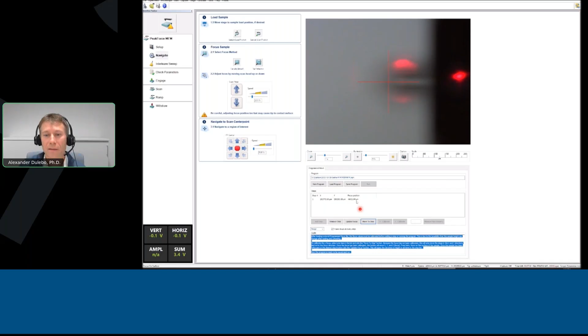So here I can also look at the oscillation of my probe during the lift mode. I can also do a quick fast thermal tune, so I can see the native resonance oscillation of my probe if I have a problem finding the right peak, for example, and I can also increase the drive if I need to. So now I would like to go straight to looking at my parameters. So I'll do a 10 by 10 micrometer scan size.